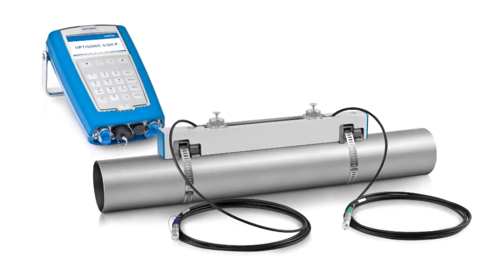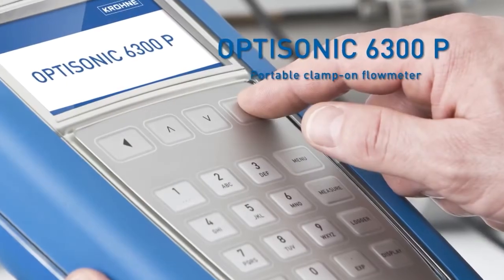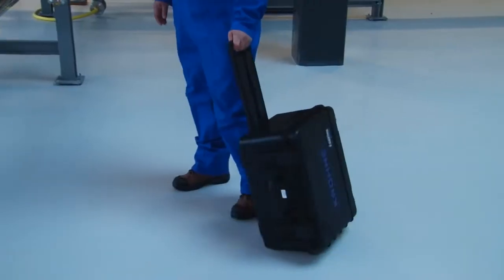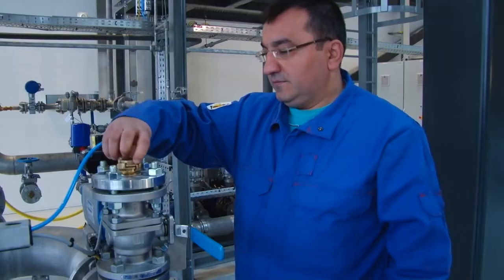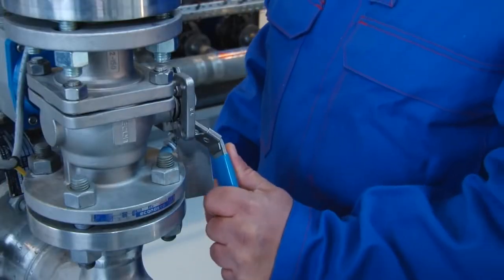Welcome to the installation instruction movie for the Krohne Optisonic 6300P portable clamp-on flow meter. Start the installation by finding an installation position with sufficient straight inlet and outlet for the clamp-on flow meter. An inlet of 10DN and outlet of 5DN is recommended. In order to commence measurement, the pipe needs to be filled completely.